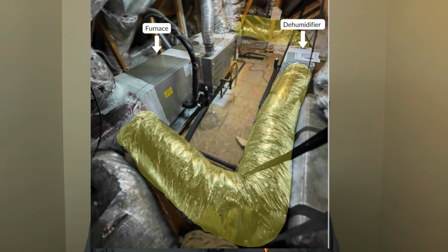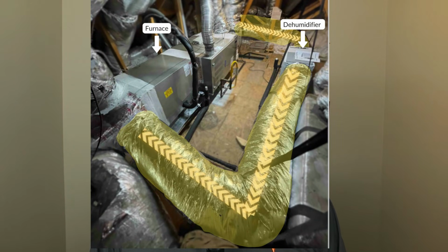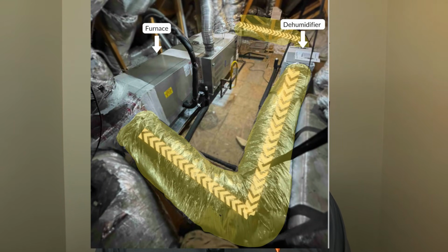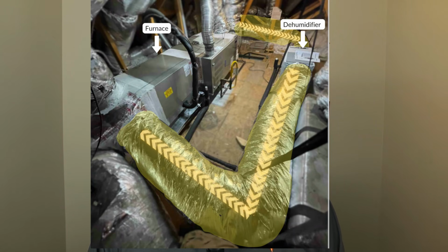The second way we install dehumidifiers on horizontal furnaces is actually very similar to the first way. The only difference is how we tie the output air to the central ductwork. So for the output air on the dehumidifier, we take a duct and tie it directly into the supply plenum of your central AC system. And as long as the supply ductwork is sized correctly, this method won't be a problem.